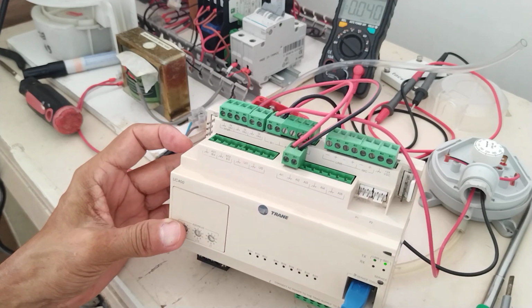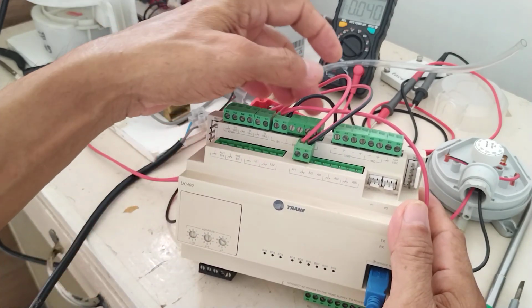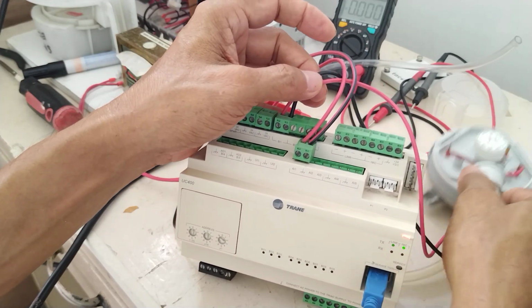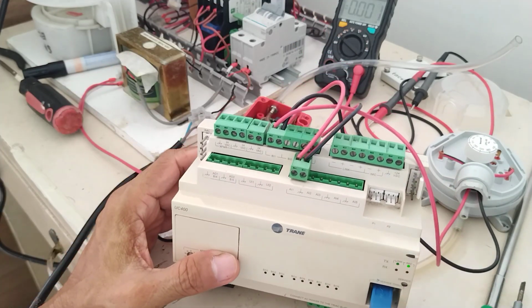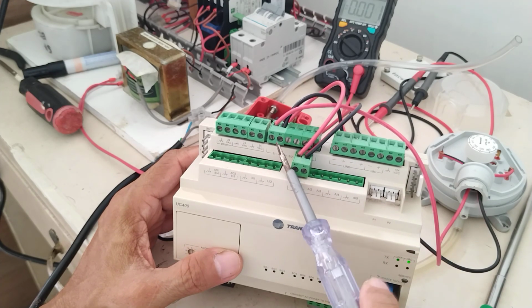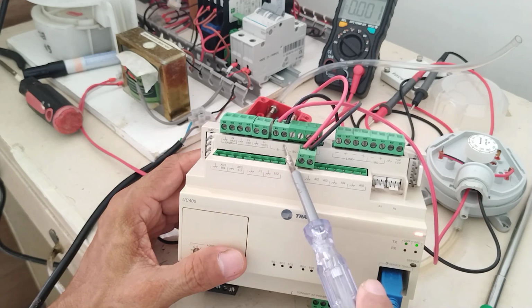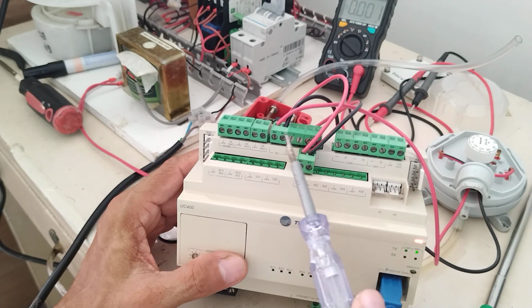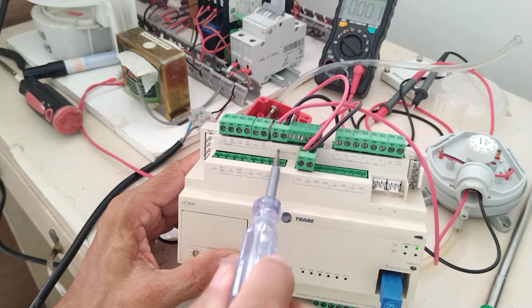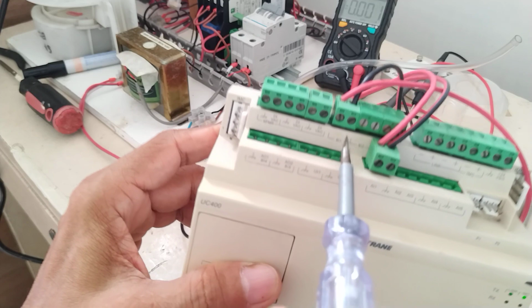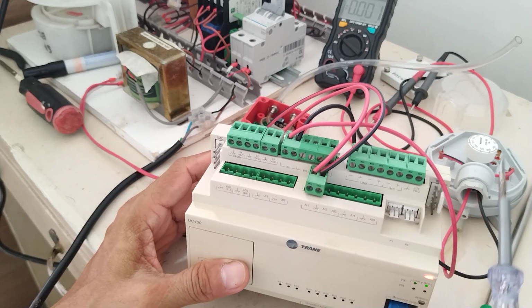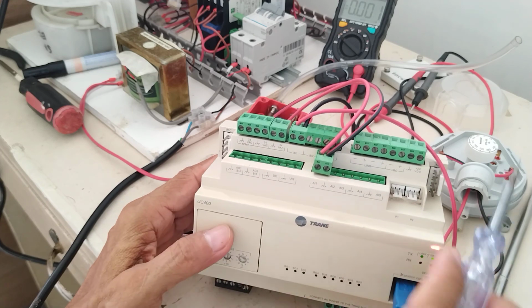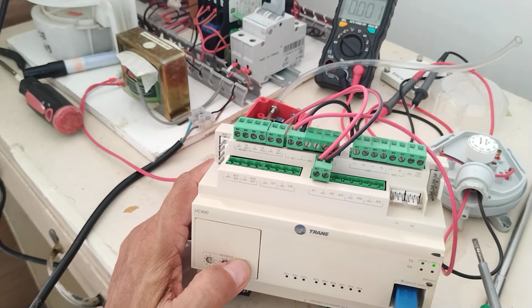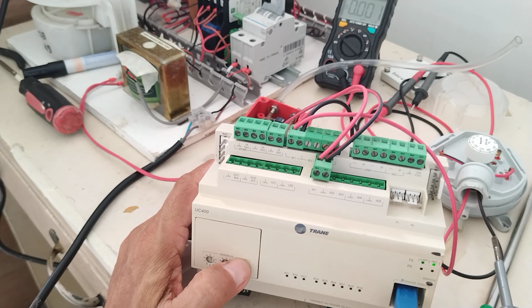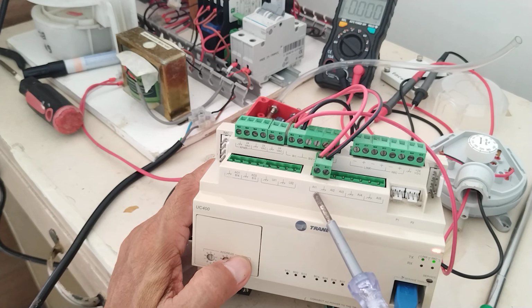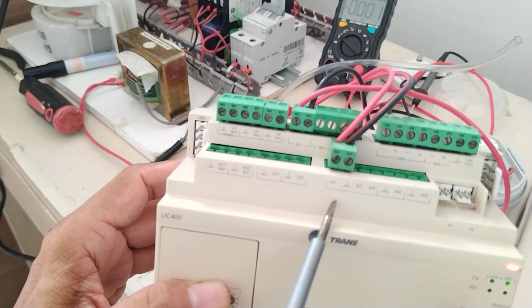Okay, now actually what I did here, I connected my differential pressure switch, the normally open contact, to the binary input. Okay, because binary meaning this is just on off, open or close. Okay, so I use it in my BI1. Okay, so BI1 here. Now, for my differential pressure transmitter, since I'm going to receive the differential pressure reading, okay? So, I need to connect it in my analog input. Okay? So, this is how you're going to connect.